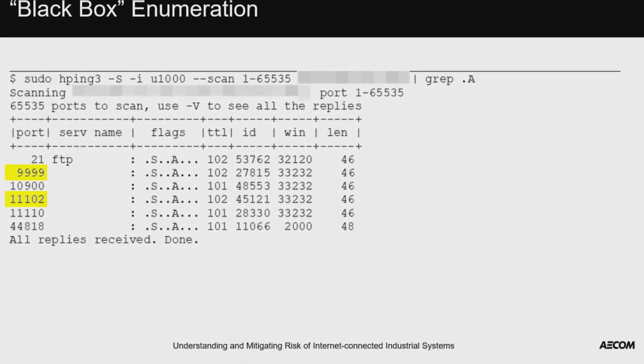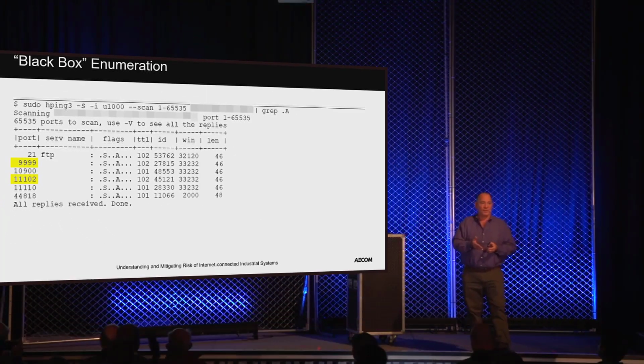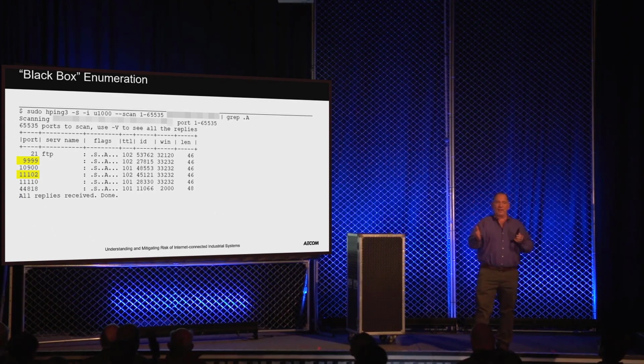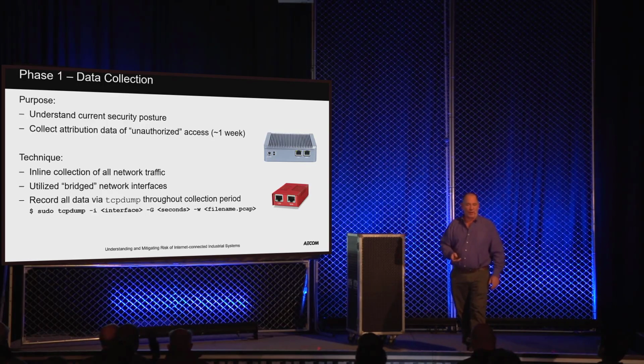It's great. Now what comes out are two very important ports. These are ports that Shodan did not characterize, but these are the ports that represent the greatest risk to this particular site, because these are the ports that allow modification of control logic and operational graphics. So now we've got even a bigger puzzle here that we're trying to piece together. But from a risk exposure standpoint, we have a serious problem.